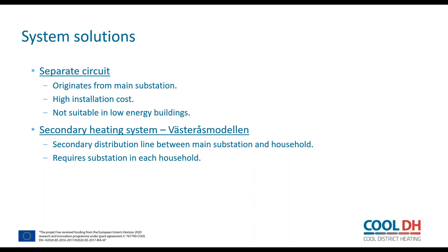there's no space heating circuits and you want to minimize the shaft space. The other solution would be to have a secondary heating system. This is also sometimes called Västeråsmodellen, after the city where it was tested. This method requires an individual substation for each household and would therefore be more suitable for new projects. It requires a lot less pipes and shaft space, but there's an additional cost for the multiple substations. The separate circuit solution has slightly higher heat losses than the other, due to the increased number and length of pipes, but you can achieve significant electricity savings with both solutions.